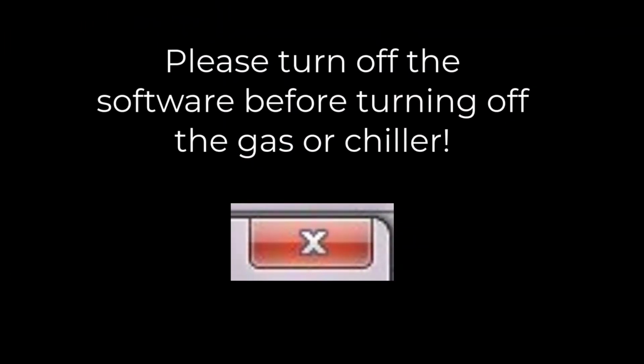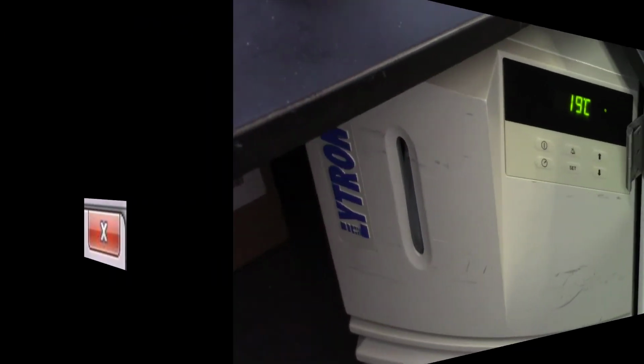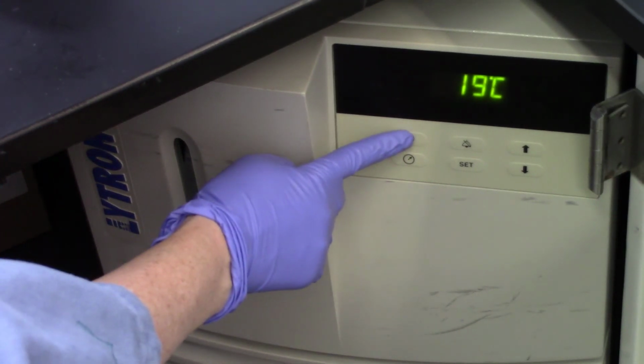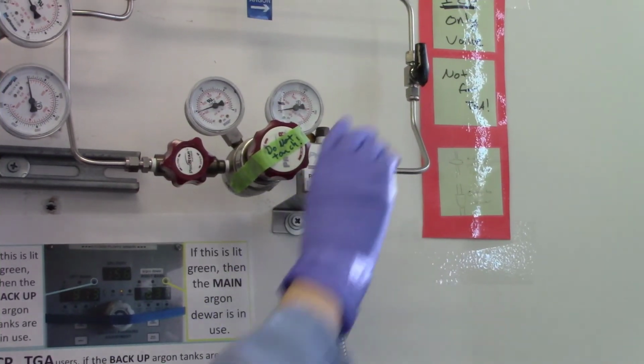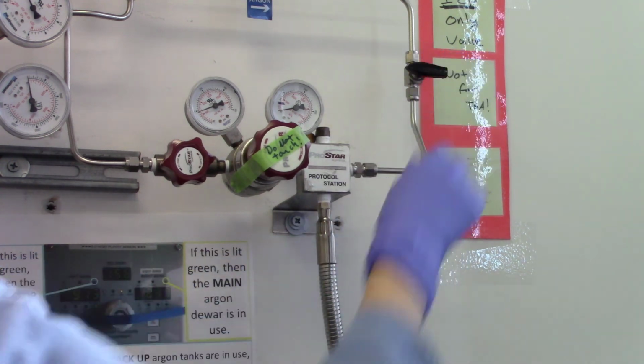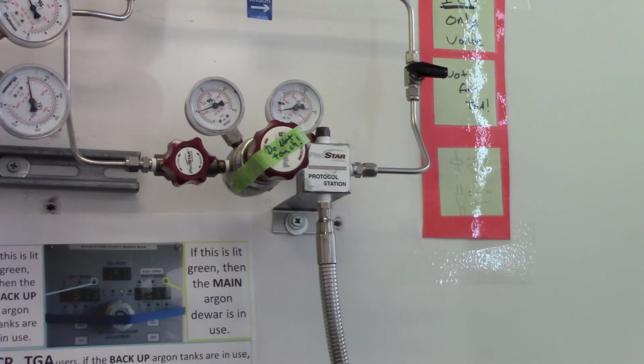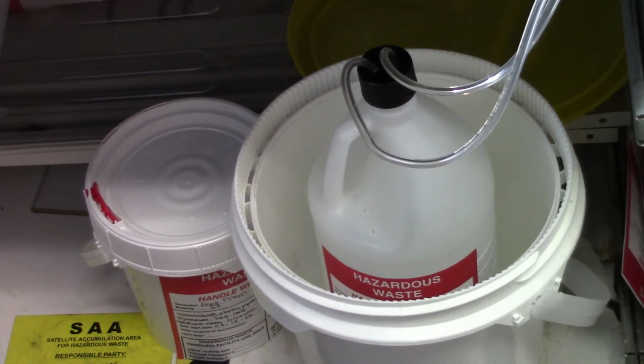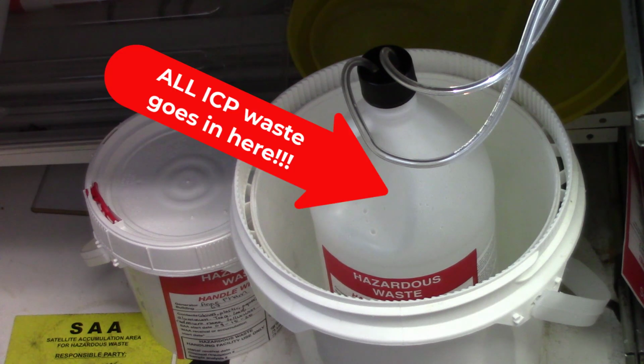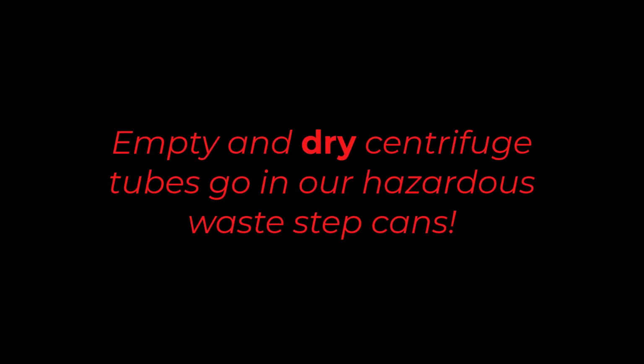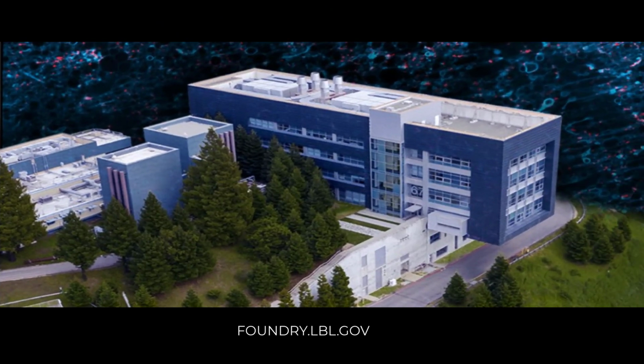Turn off the software after saving your data, then power down the chiller. Close off the argon supply to the dewar, sign the logbook, and you're nearly done. Please do not forget to dump any residual solvent into the waste stream under the instrument, and after your centrifuge tubes have dried, dispose of them in a step can. That's about it for the ICP. If you have any questions, please contact a staff member. We are always here to help.